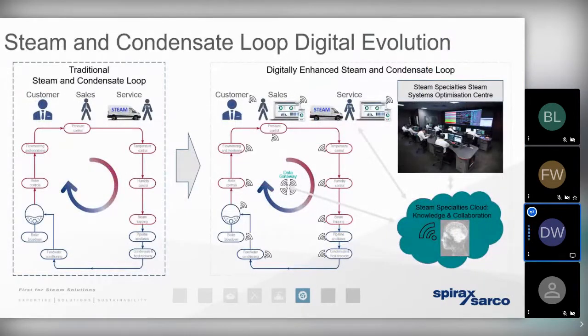We can move towards a digitally enhanced steam system. So if we consider a traditional steam system, the processors are typically capable of sending a signal back from the individual control valves, steam traps, variable speed drive pumps, boiler controls, flow meters, etc. Typically, they can send a signal back to a PLC or a BMS for diagnosis at some point in time. Whereas if we can move towards a digitally enhanced system, then all of these various components and controls could be capable of interacting with each other and sending that information back remotely over a cloud-based storage system. So that information can be downloaded and interrogated anywhere in the world.